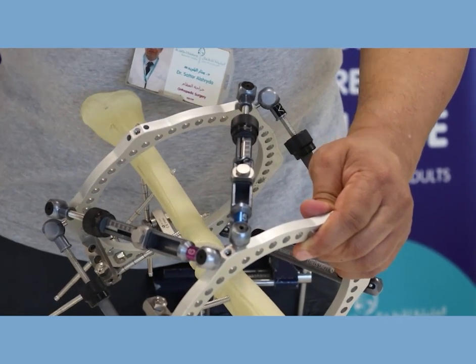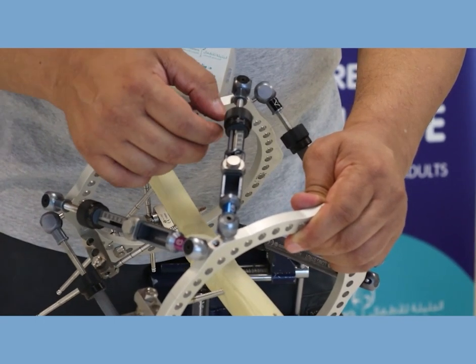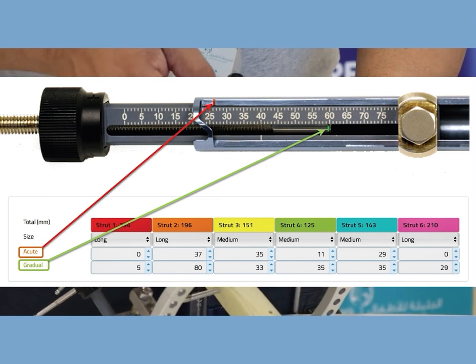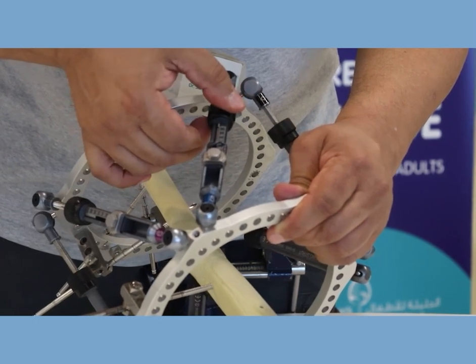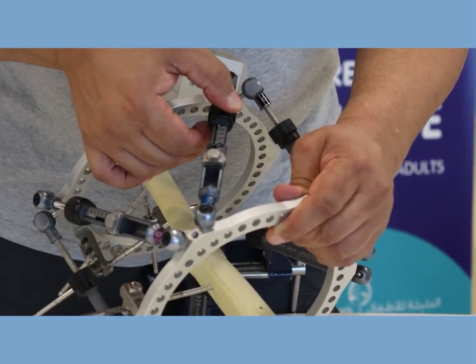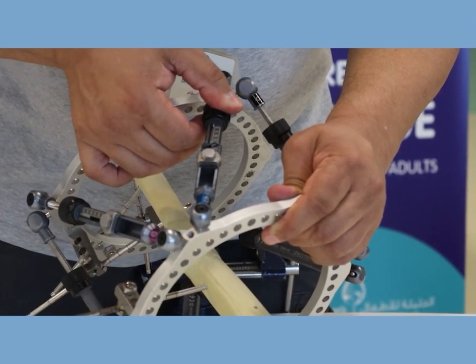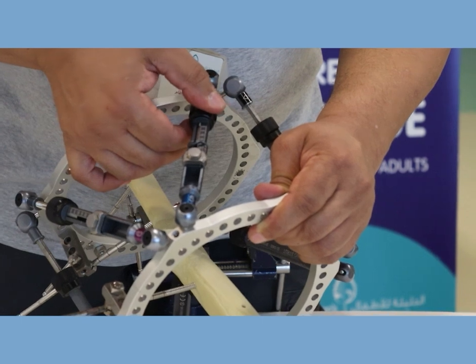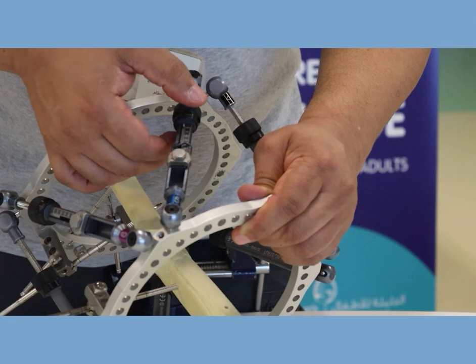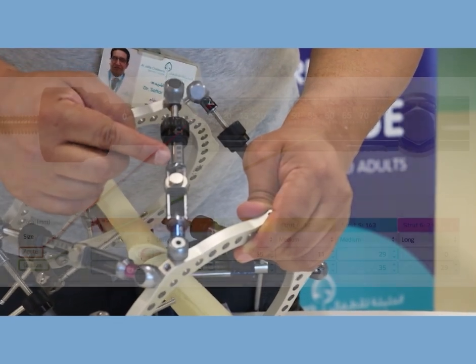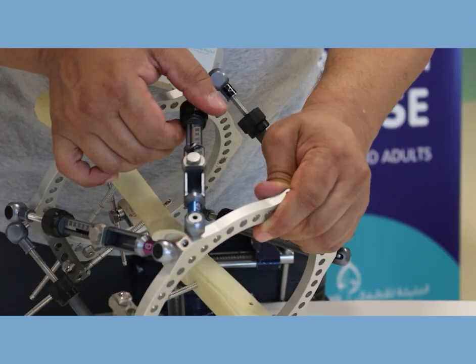Interestingly, on the TL Hex strut when you lengthen them the number gets smaller not bigger. So this is something to bear in mind. If this strut according to the program needs lengthening, you turn it. When you turn half a turn you hear a click. Then you have to pull it up and you turn it again and you hear another click. You see the green marker change according to the numbers, and this is what the patient does as they look at the program.